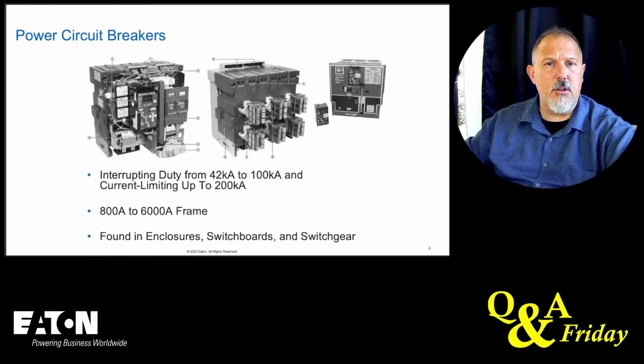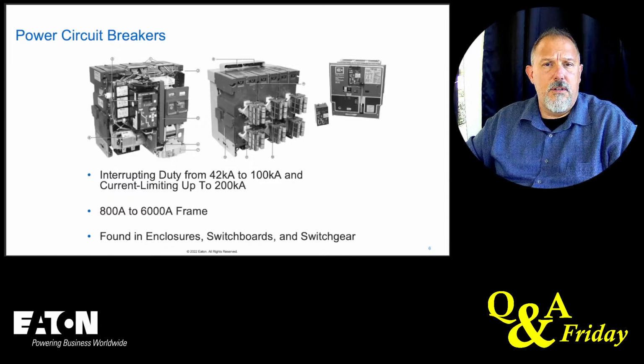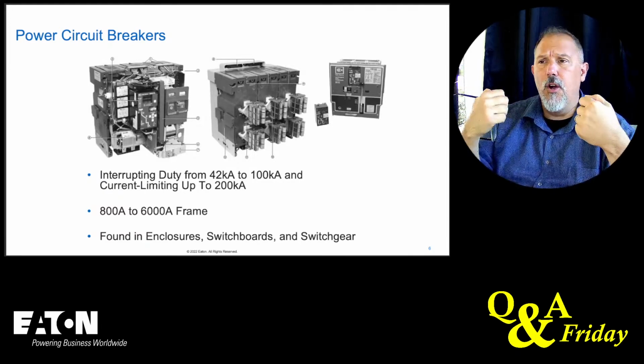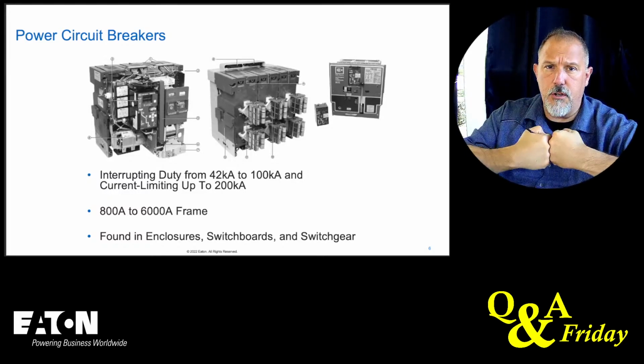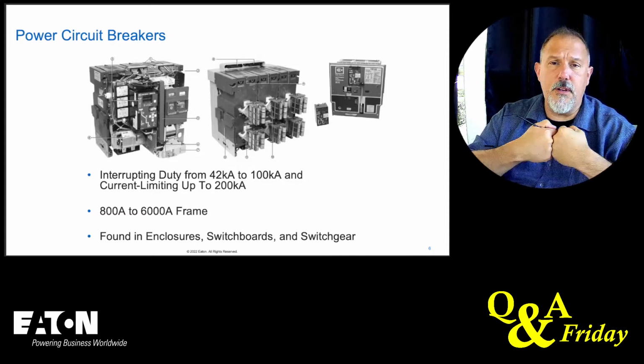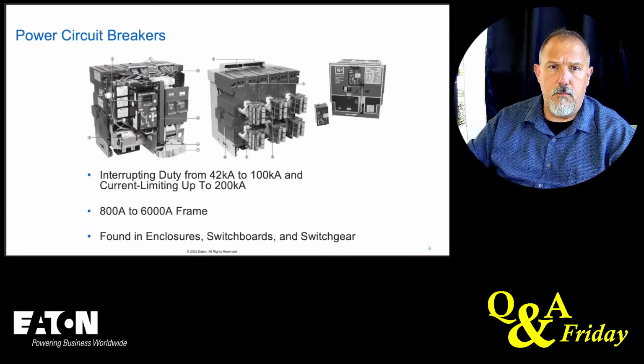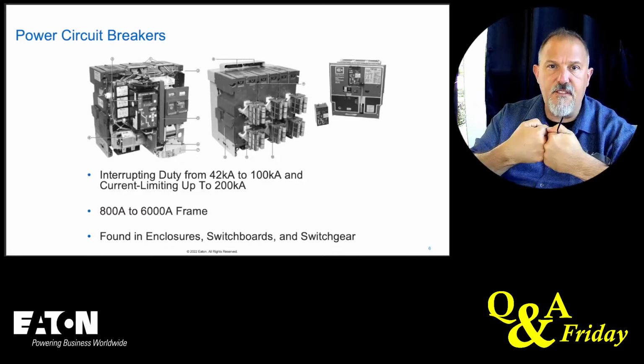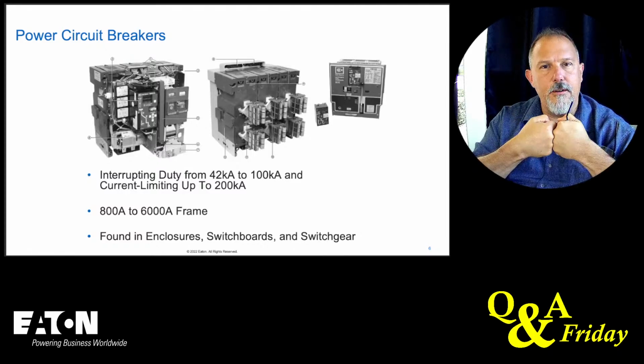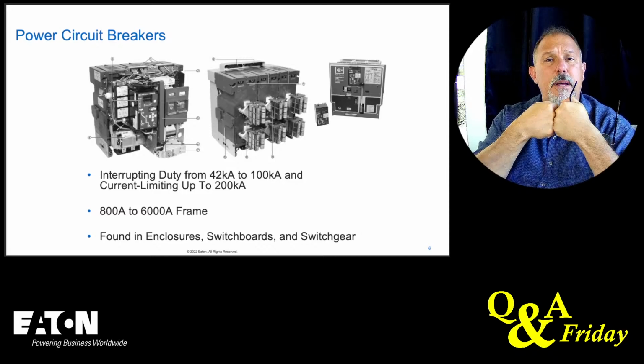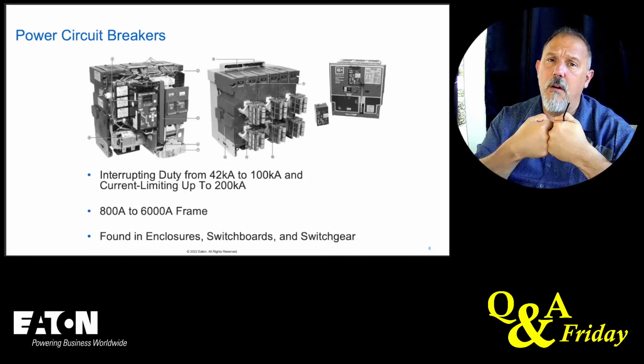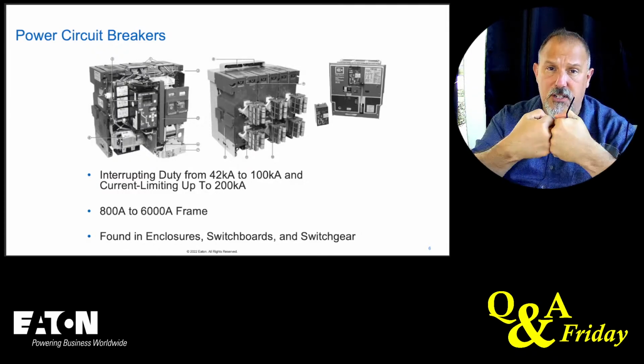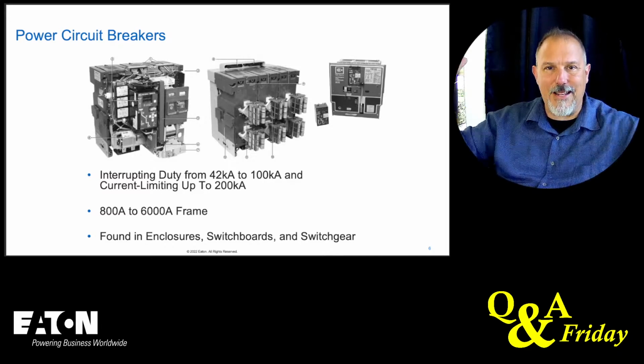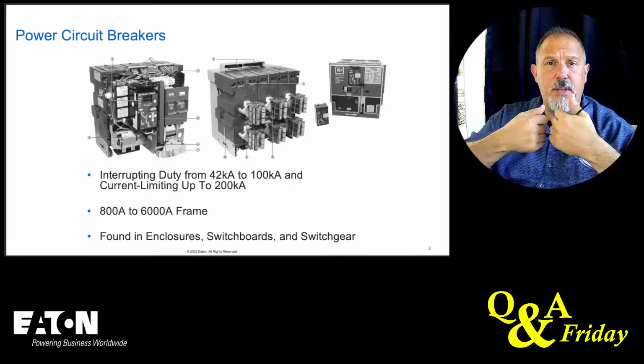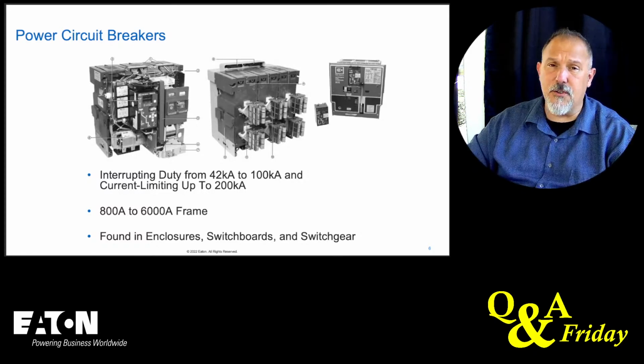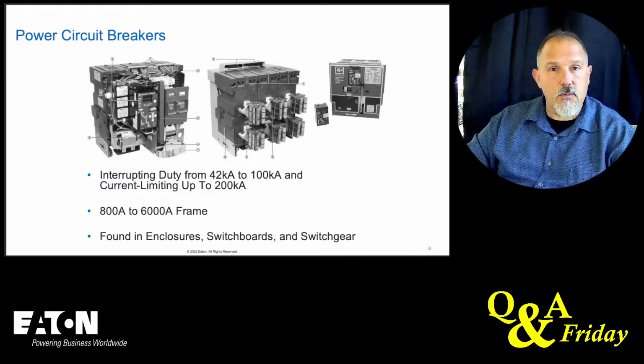Say you needed your contacts closed for 100,000 amps for 30 cycles. That's a lot of magnetic forces that want to push those contacts apart. The circuit breaker that's going to hold those contacts closed for up to 30 cycles at 100,000 amps is not going to be some scrawny little, tiny little molded case circuit breaker. No, you got to bring springs and beef to the table to hold those contacts closed, because you don't want chatter. You want those contacts to remain closed, and I got to bring heavy-duty mechanisms to get that done. And it's not going to be in a small format. And not only does the circuit breaker need to be braced to be able to hold those contacts closed, but the entire structure that it's in has to be braced for those high fault currents being held together for that long period of time. 30 cycles is an eternity when it comes to currents. So that's why you've got the beef.